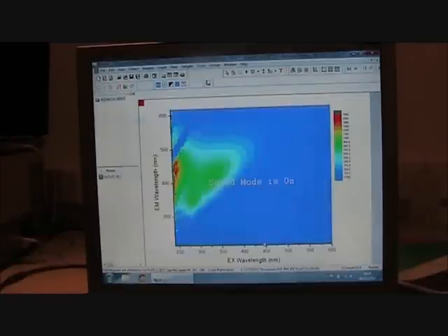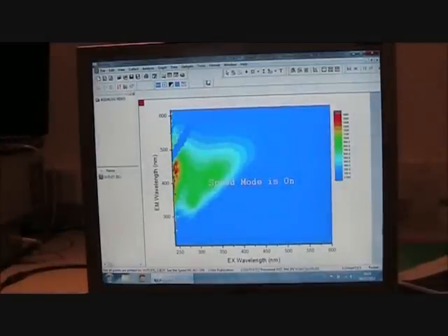So there we are, a total time of approximately 2 minutes, an EEM generation out in the field in a fraction of the time a scanning spectrofluorimeter would take.